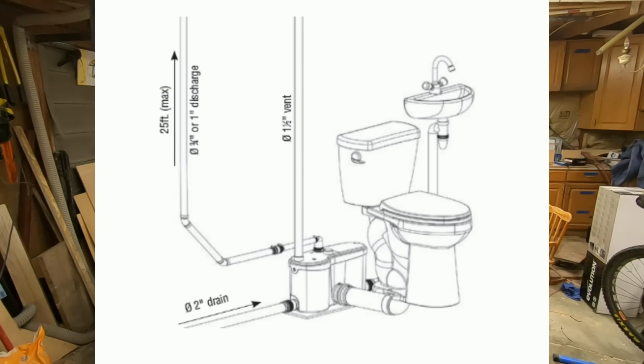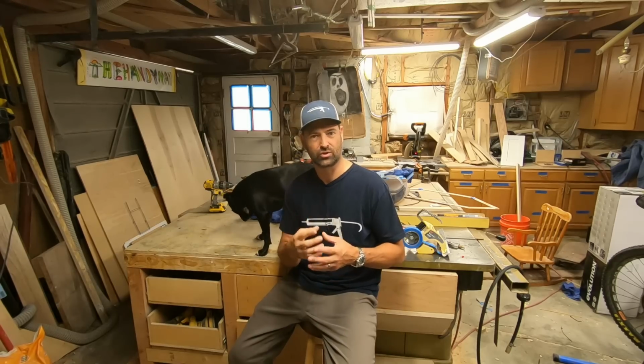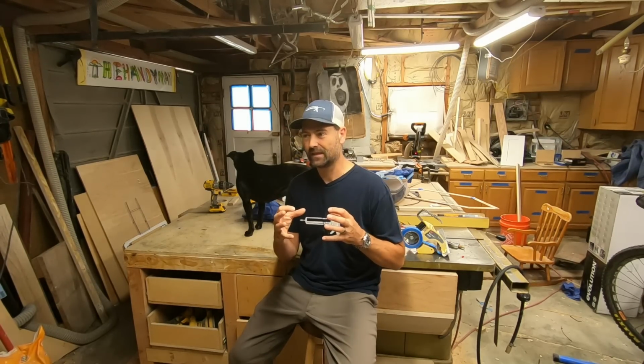And what I found was a nail. A nail jammed up in the teeth of the grinder portion of that pump. Let me tell you, I was surprised. The blades on that pump were super thick, very sharp, not enough to go through a nail. Now you're probably wondering, where the heck did that nail come from?